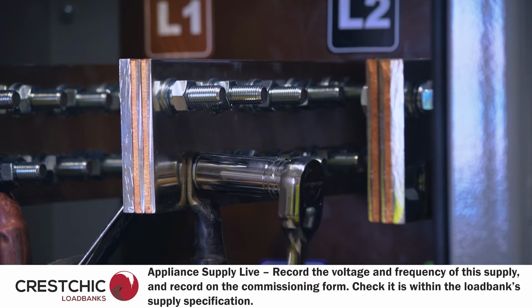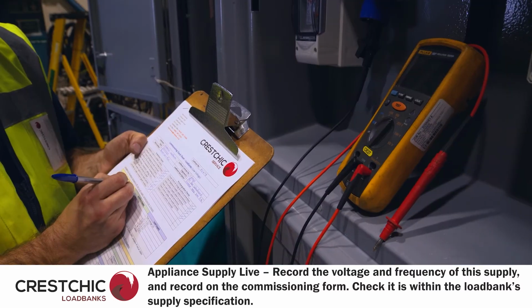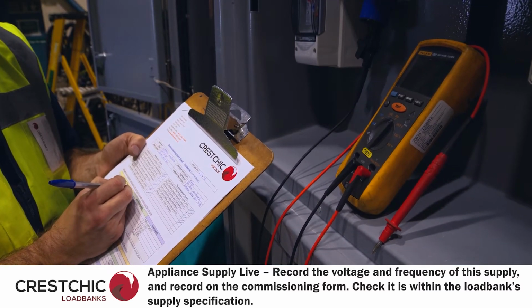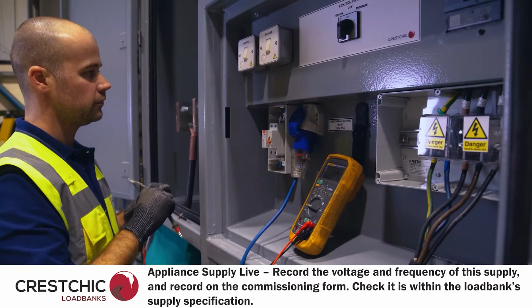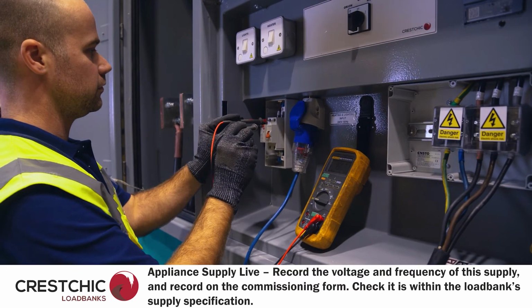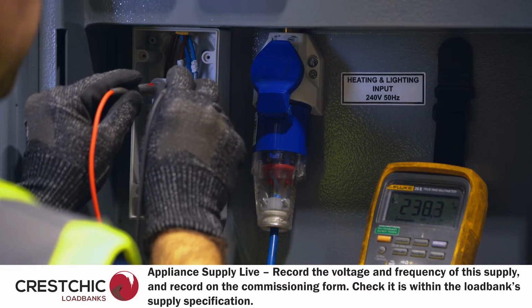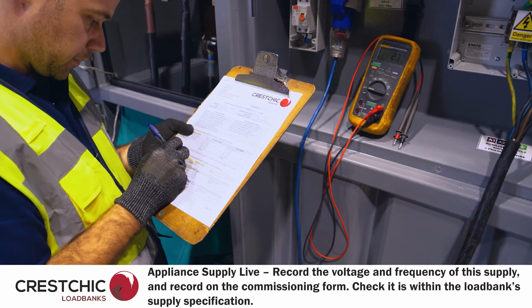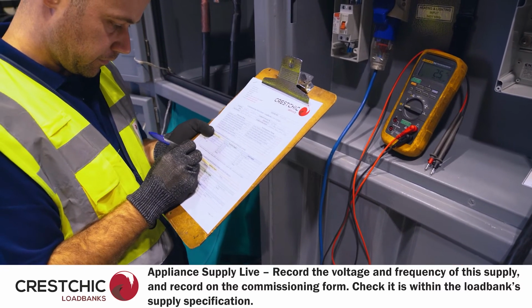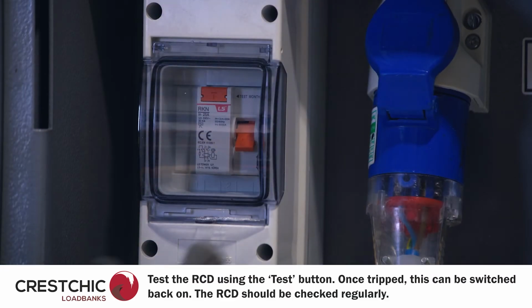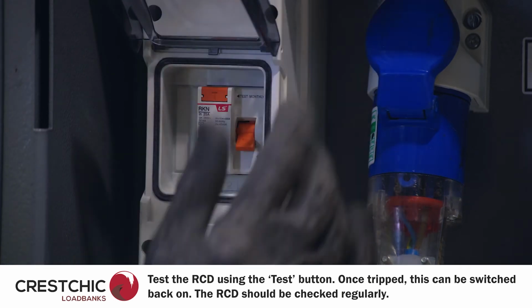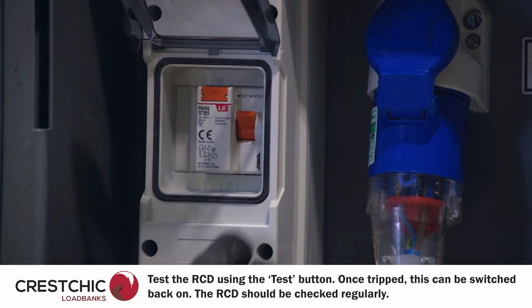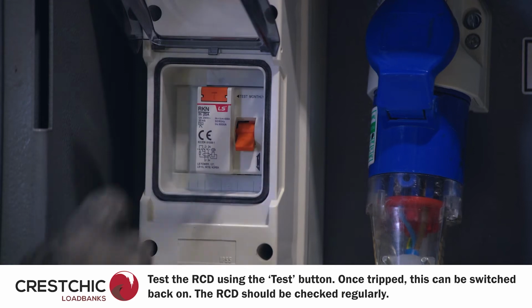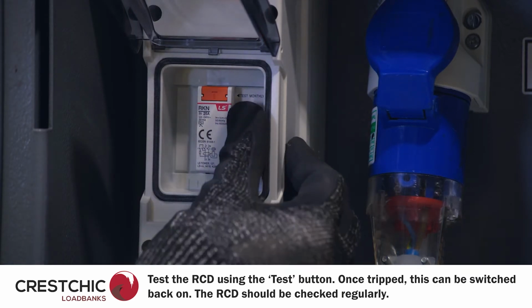Once the supplies are connected to the load bank, these can be turned on in turn and various checks can be performed. Firstly, the appliance supply can be turned on. Once on, the voltage and frequency should be checked and recorded on the commissioning form. The RCD should be checked for function. With the RCD on, press the test button to trip the RCD. Once completed, the RCD can be switched back on.